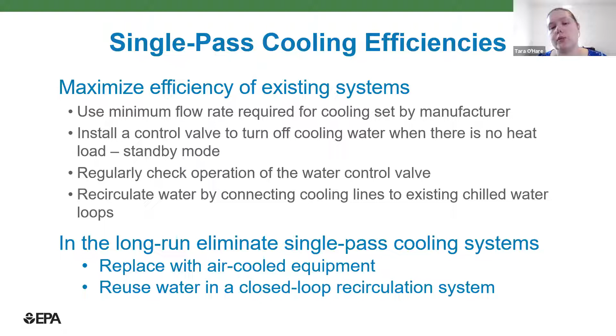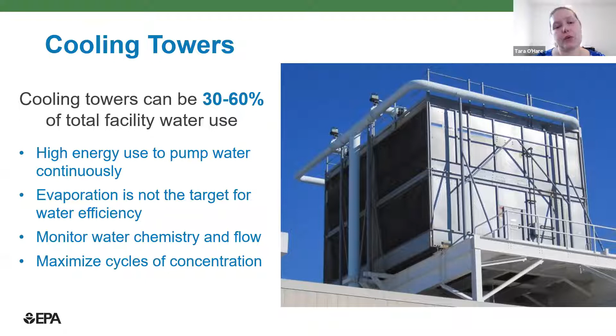Cooling towers can be 30 to 60% of your facility water use, and it uses a lot of energy to pump the water through the system. So it can be a really big target for water efficiency and energy efficiency. One point to make is that evaporation is not the target for water efficiency. The evaporation is the main function of the cooling tower to remove the heat load, which we want to happen so you don't have overheated equipment. So we don't look at the evaporation as a thing to minimize in this case. We encourage you to do other things to monitor water chemistry and flow instead, and to maximize cooling cycles of concentration.